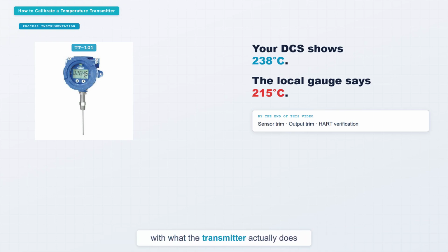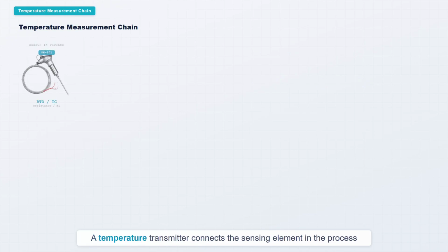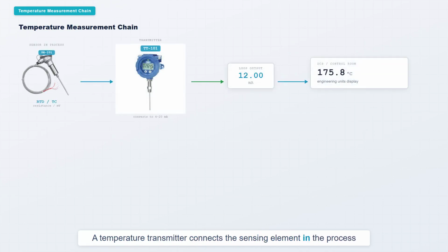Let us start with what the transmitter actually does. A temperature transmitter connects the sensing element in the process to your control system. The sensor, an RTD or thermocouple, sits inside a thermowell in the pipe. It produces a resistance or millivolt signal that changes with process temperature. The transmitter converts that signal into a 4 to 20 milliamp loop current. 4 milliamps is the lower range value. 20 milliamps is the upper range value. Your DCS reads this current and converts it back to degrees Celsius or Fahrenheit.